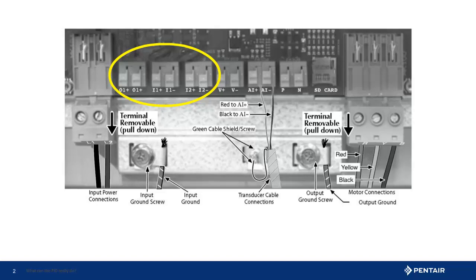From the factory, input and output are unprogrammed, but can be programmed to run, fault, or run at a secondary pressure depending on how you program the input and what is connected. An output tells the observer what the drive has done or to do something when the programming calls for the relay to close. Remember, from the factory the relay is not programmed but can be programmed to fault or run.